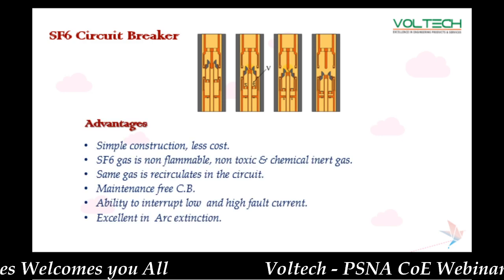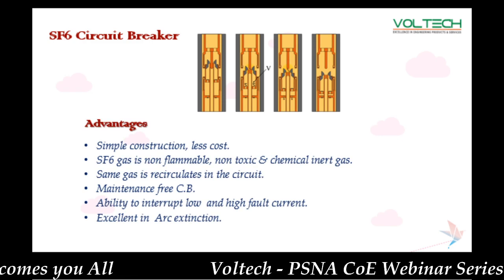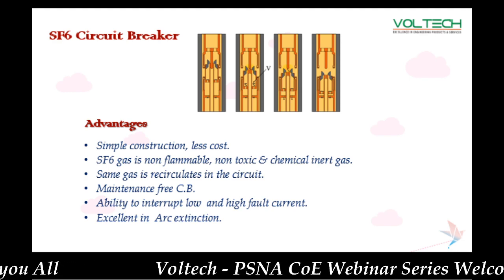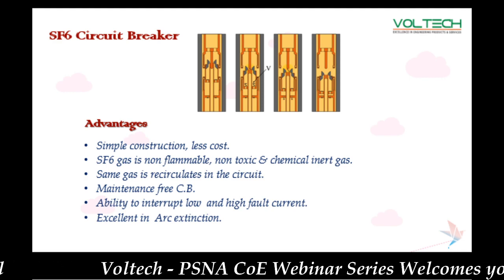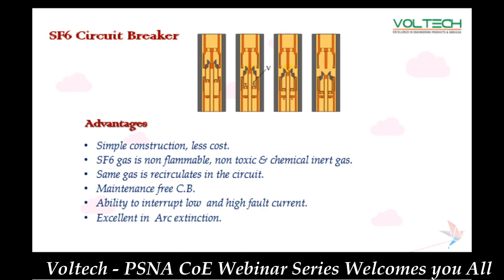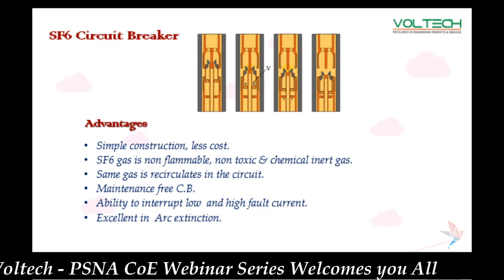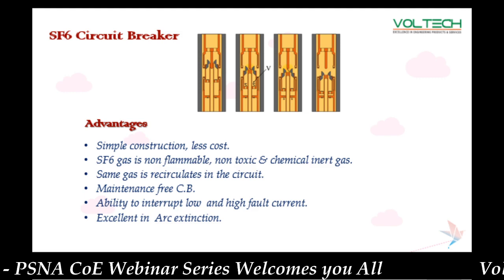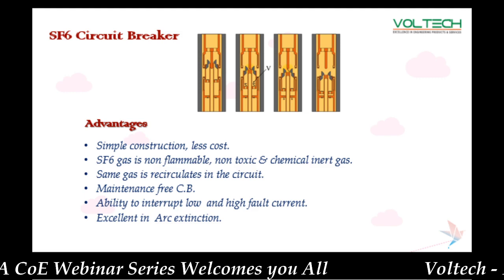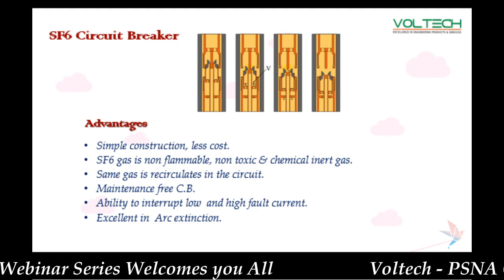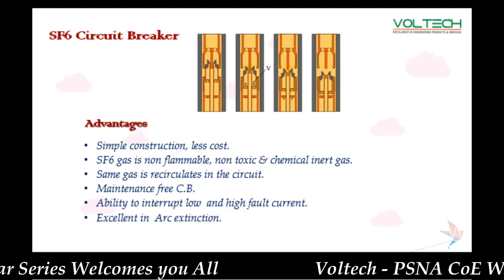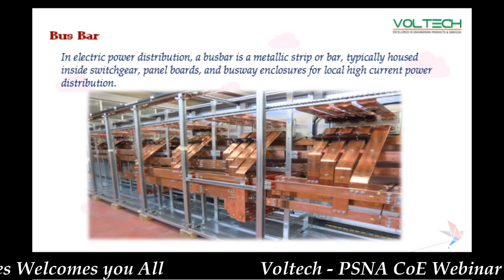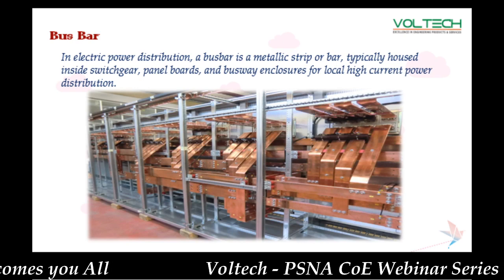The advantage is that it's simple. Compared to vacuum or any other types, the cost is low. If you go for higher kV, the cost is low and it's maintenance free, able to interrupt high fault current. It can also withstand high fault current. Excellent arc extinguisher. So this is the busbar arrangement.